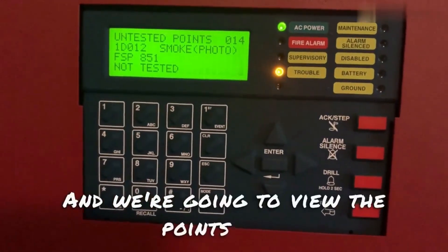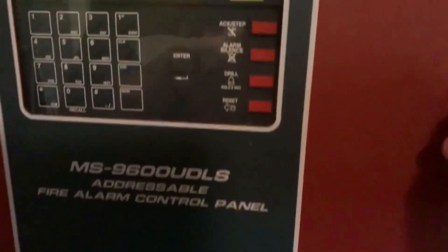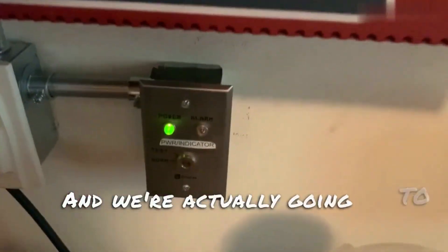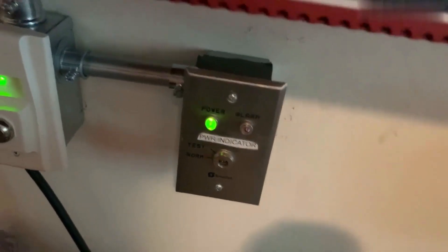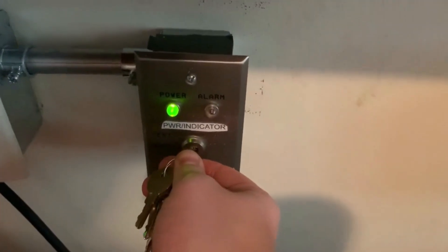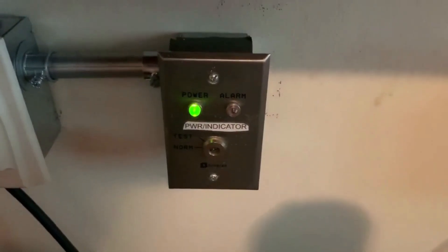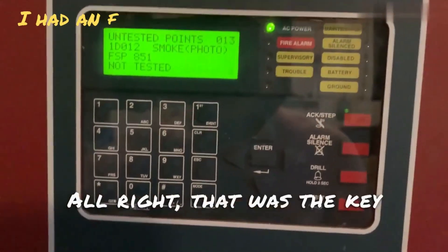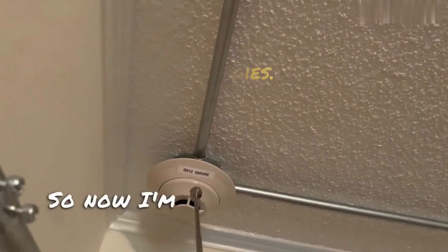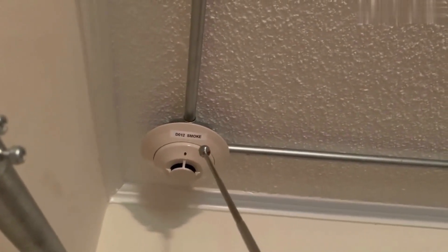We're going to view the points that have been tested and not been tested. Alright, the panel's now in walk test, and we're actually going to start by doing the 2098-985 key switch first. That was the key switch. Now we're going to go ahead and go over and test the Fire-Lite SD355. I'm just going to hold my magnet up to here, and it'll activate the SD355.